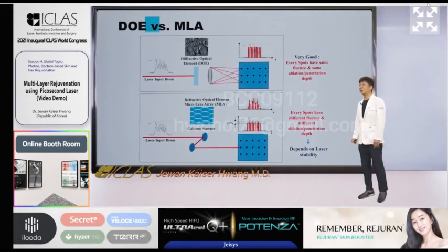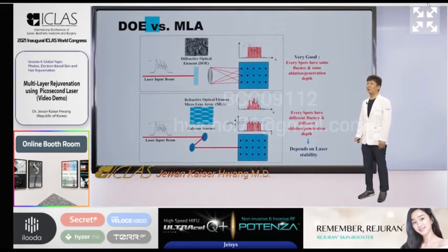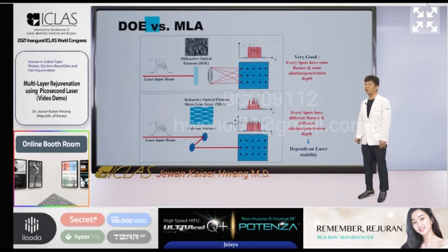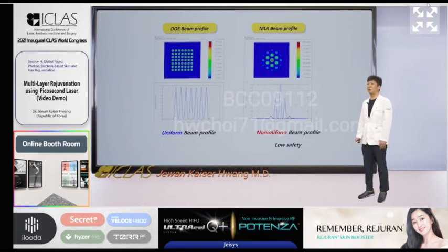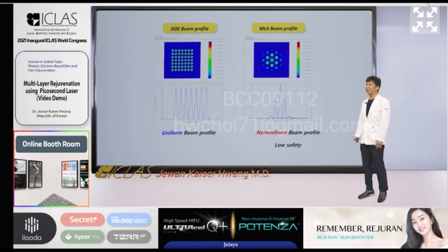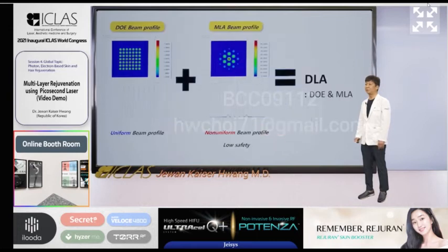So far, I have looked at the pros and cons of MLA and DOE and have seen treatments using them. Now let's talk about how to combine these two advantages. DOE has a homogeneous microbeam, but power density is lower due to energy loss from diffraction — about 20%. MLA can increase power density, but safety is lower due to inhomogeneous beam profile. So I decided to combine these two and make a DLA handpiece.